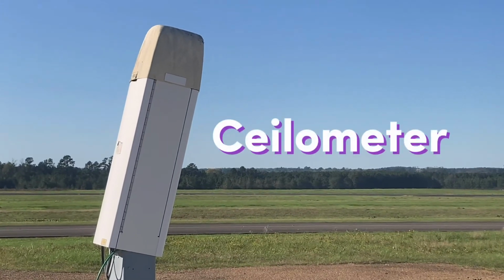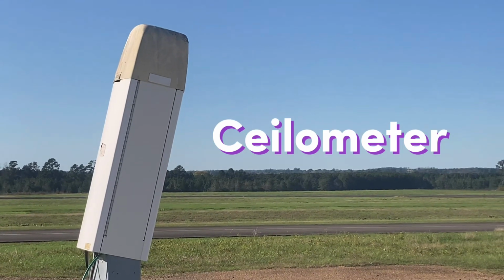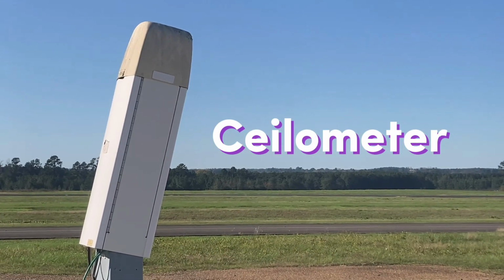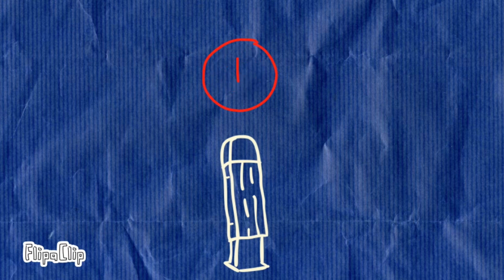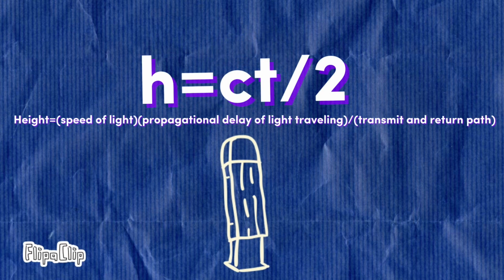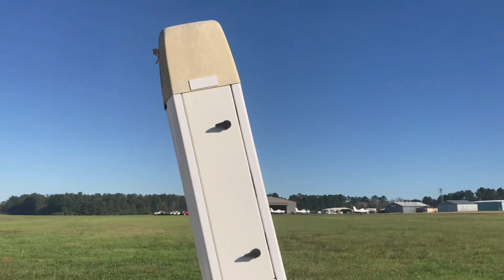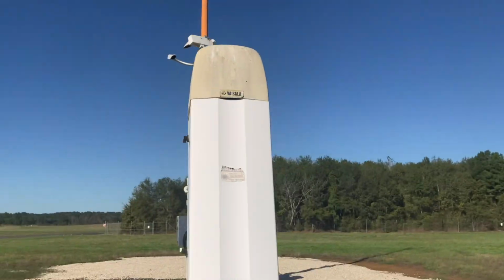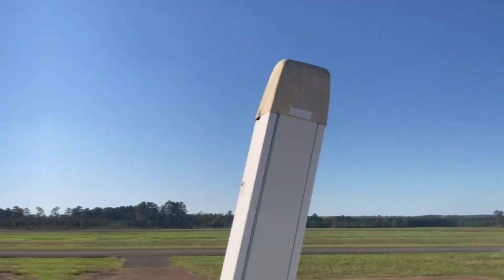Let's start with the ceilometer, an instrument that uses light beams to measure the heights of clouds. The ceilometer shoots a laser beam up to a cloud and measures the amount of time it takes that light to travel back. It determines the height of the cloud using this formula and sends that information to the AWOS's computers. The ceilometer also has the ability to tilt up to 12 degrees to get more accurate readings.